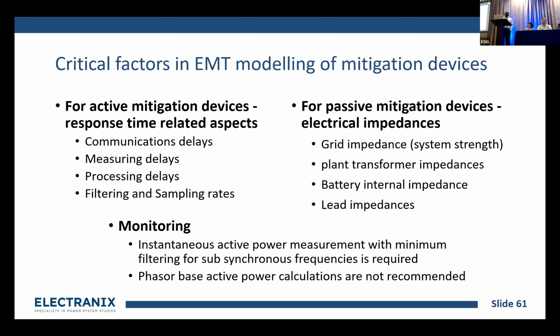The typical smoothing constant in these meters is usually 20 milliseconds. If you use a 20 millisecond real pole filter on instantaneous power, what you are essentially doing is cutting out any frequencies above 8 hertz. That number is too big, so you need to use a very small filter time constant, probably around 1 millisecond. That will make sure you are only filtering out very high frequencies, not the components that we are interested in.